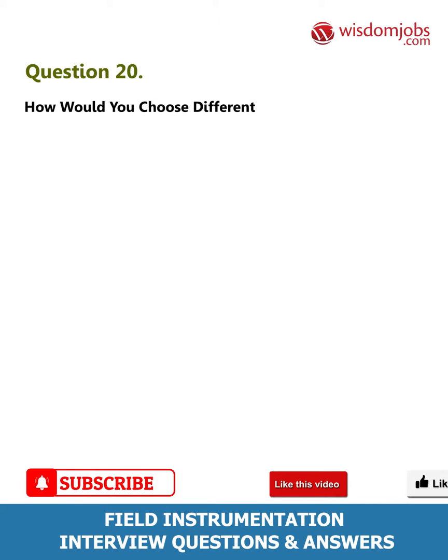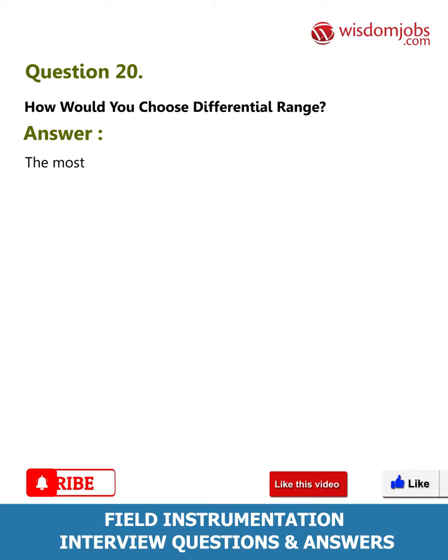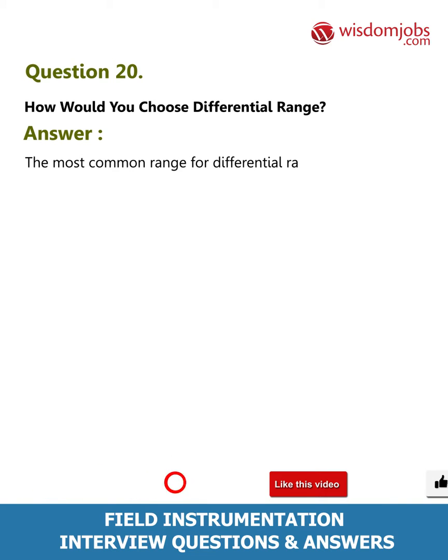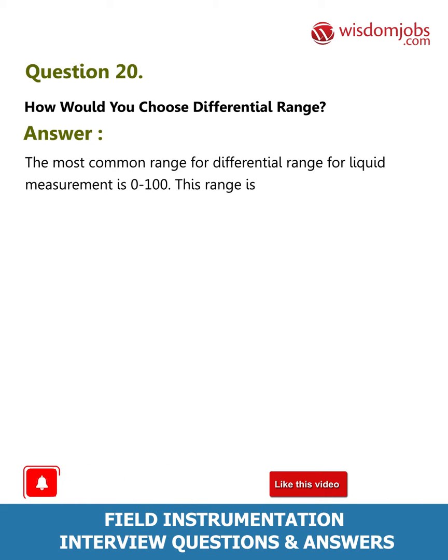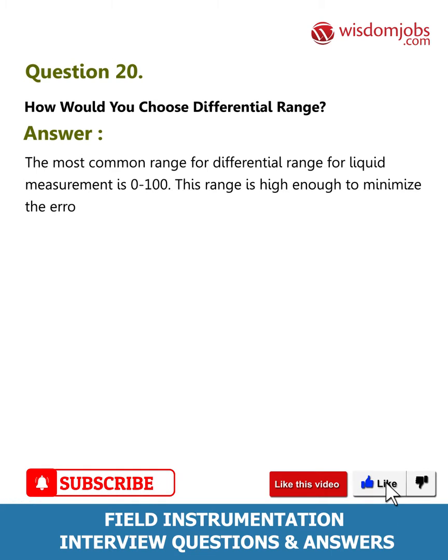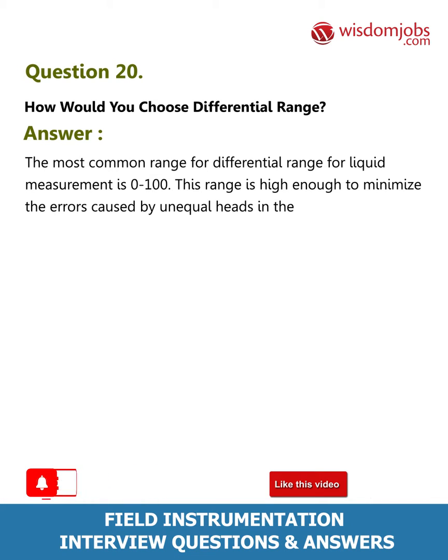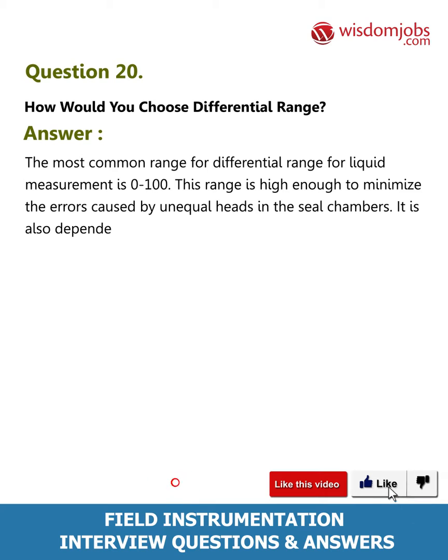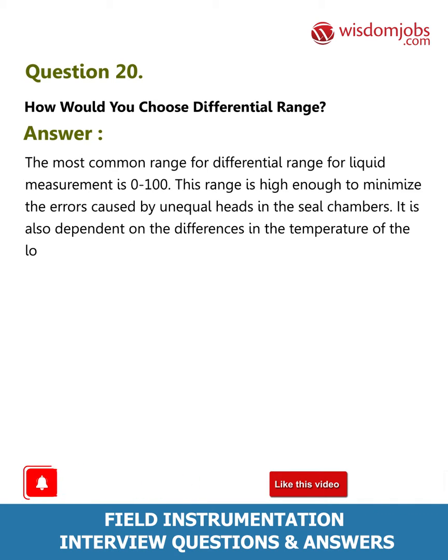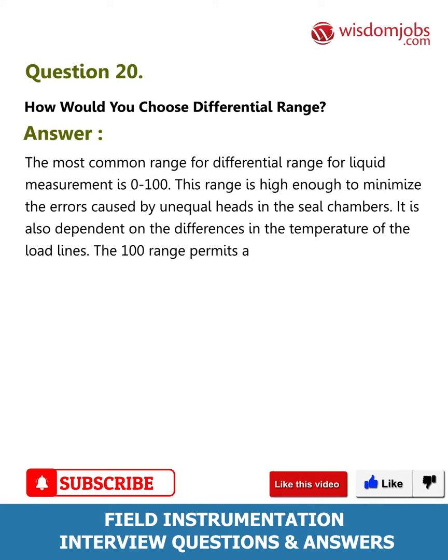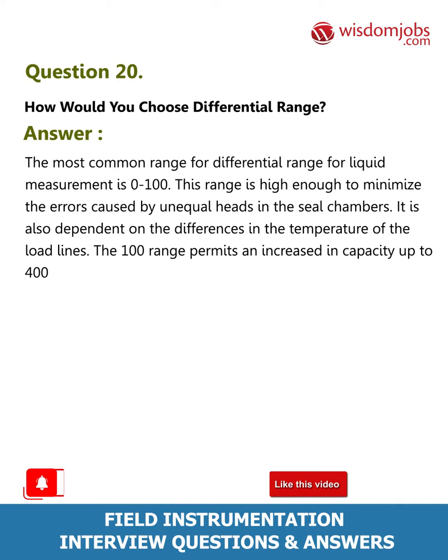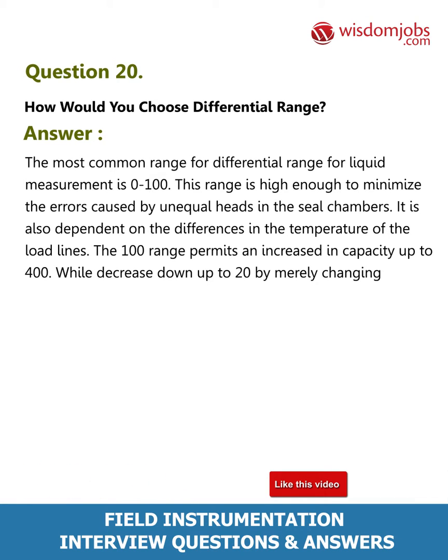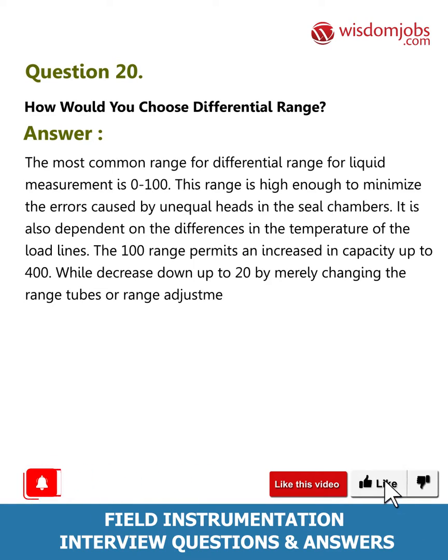Question 20: How would you choose differential range? Answer: The most common range for differential measurement for liquid measurement is 0 to 100. This range is high enough to minimize errors caused by unequal heads in the seal chambers, and is also dependent on differences in the temperature of the lead lines. The 100 range permits an increase in capacity up to 400, while a decrease down to 20, by merely changing the range tubes or range adjustments.